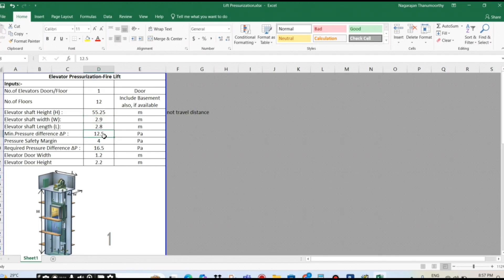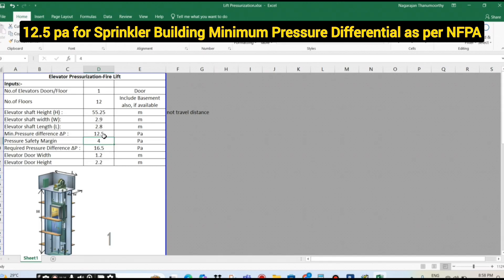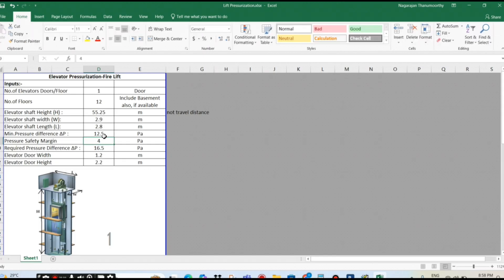And minimum pressure difference — yesterday I told you, for the sprinkler building minimum 12.5 Pascal we have to consider. So that 12.5 Pascal, the same I consider, but yesterday I told you one more point also. So if your client is accepting, then you can go with the minimum, or minimum 4 Pascal extra. So that minimum 4 Pascal extra only I have considered here, but if your client says no, no issue — we can consider directly as per the standard minimum requirement. So in this case, we are going with the optional one — but normally I consider 4 Pascal extra, I don't reduce that one. So 16.5 Pascal overall we are considering.